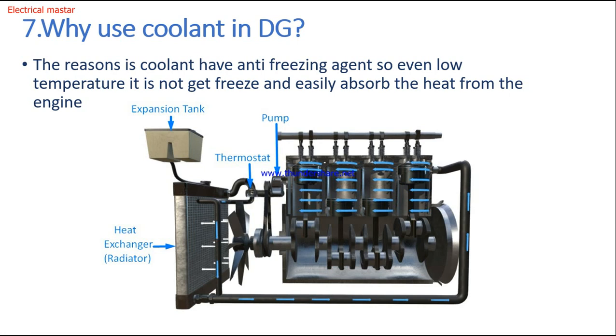Seventh question: why do we use coolant in a diesel generator? Coolant has anti-freezing properties, meaning it does not freeze even at low temperatures. It also easily absorbs heat from the engine. You can see this picture — from the radiator tank, coolant moves from the bottom into the diesel engine cylinder side, then returns through a thermostat back to the radiator tank. Inside the radiator tank there is a heat exchanger, and the radiator fans cool the heated coolant using atmospheric air, and the same coolant returns to the same process.